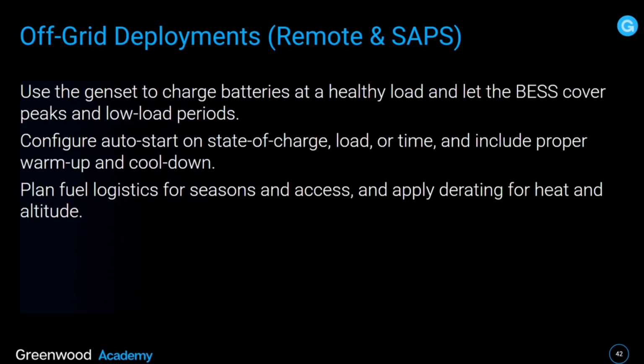Use the genset to charge batteries at a healthy load and let the BESS cover peaks and low load periods. Configure auto start on state of charge, load, and time of day, and include proper warm-up and cool-down. Plan fuel logistics for seasons and access, and apply derating for heat and altitude.